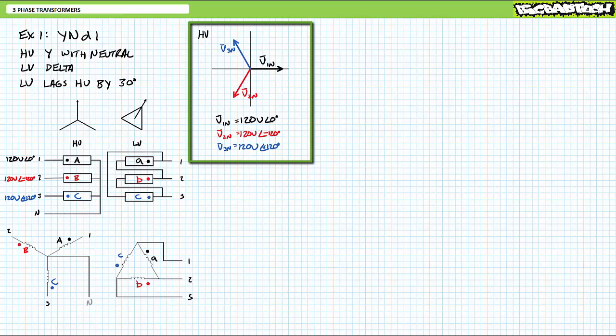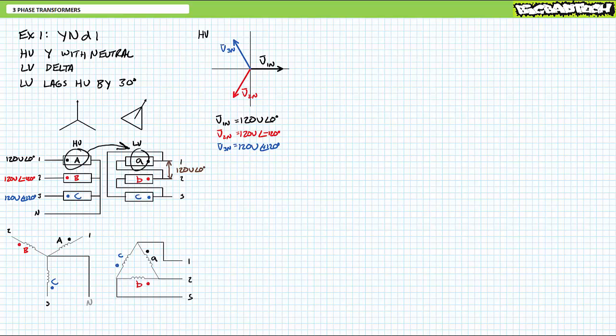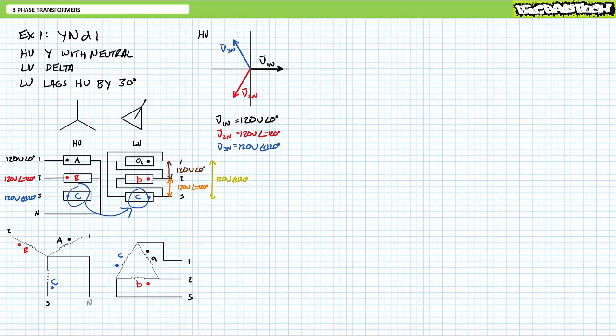Let's say we're making use of light industrial 120 volt line-to-neutral, 208 volt line-to-line, 60 hertz three-phase AC, and a transformer with a one-to-one turns ratio. High voltage winding capital A gets mapped to low voltage winding lowercase a with no phase shift, such that the line-to-line voltage between line one and two on the low voltage side would be 120 volts at an angle of zero degrees. Similarly, capital B maps to lowercase b with no phase shift, giving 120 volts at negative 120 degrees between lines two and three. Finally, capital C maps to lowercase c, giving 120 volts at an angle of 120 degrees between lines three and one.